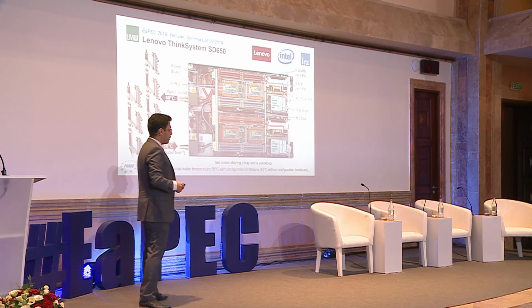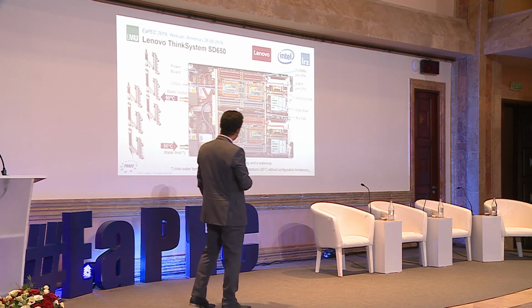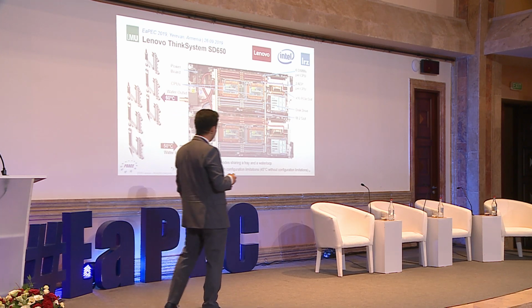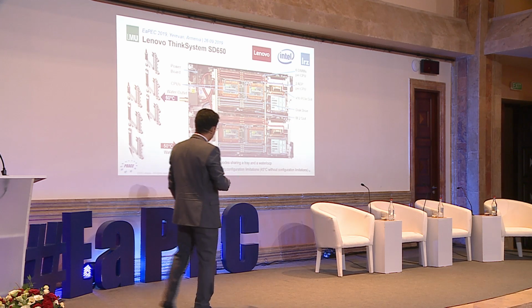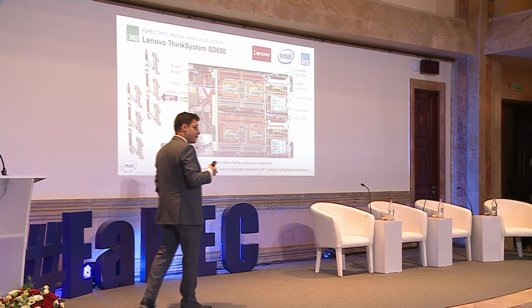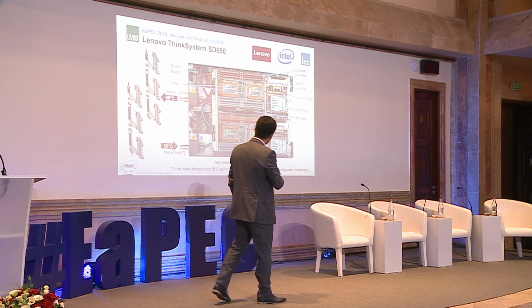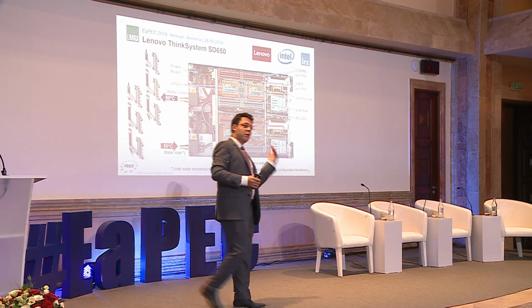But with SuperMUC NG we went even further and increased the withstand. With Lenovo and Intel together, we worked to design a node that will now withstand inlet temperatures of up to 50 degrees C. Typically, depending on your workload, your outlet temperature can be as high as 60 degrees C. Usually, to be even more energy efficient, we pipe this outlet temperature to special devices called adsorption chillers to generate cold water.